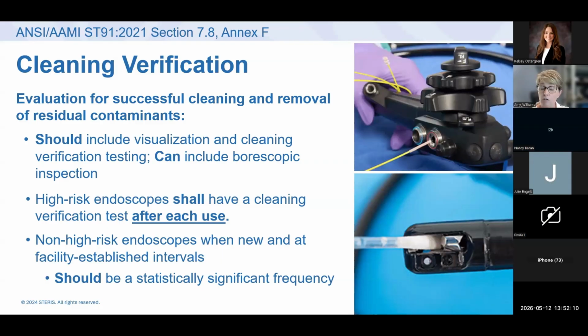Non-high-risk devices also should have cleaning verification testing performed at a statistically significant interval. So a percentage of those devices, non-high-risk devices, should be tested with cleaning verification testing at an established interval that is statistically significant. Maybe monthly, maybe quarterly. Again, it depends on your volume. It depends on your facility's individual needs. Okay. But they should be done. And a lot of folks don't realize that.